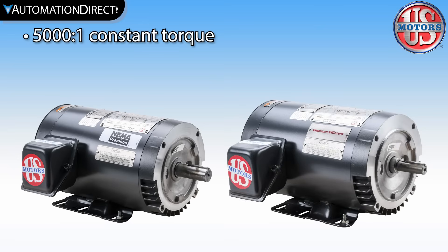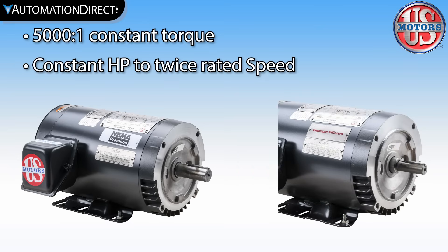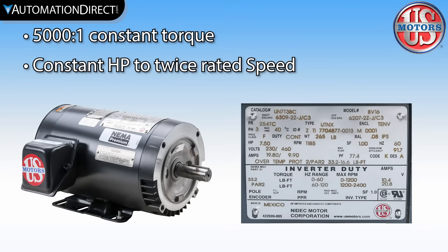These are capable of a 5000:1 constant torque speed range, meaning they are designed to handle the excessive heat that occurs in applications that require full torque at zero motor speed, and they allow constant horsepower operation to twice base speed.